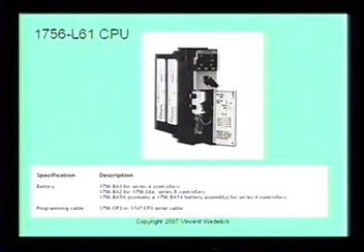The 55 controllers, if you've got that little bitty battery right here, you can see this battery's right here, okay? If you've got that little bitty battery right there, it will die within 40 days or something crazy. You have to put the larger battery pack in there, and then that'll last for, I can't remember exactly what it is. I think it's in the slides here. But make sure that when you buy these that you go ahead and upgrade to the L61. It's actually cheaper than the 55 controllers, so it's actually a good thing.